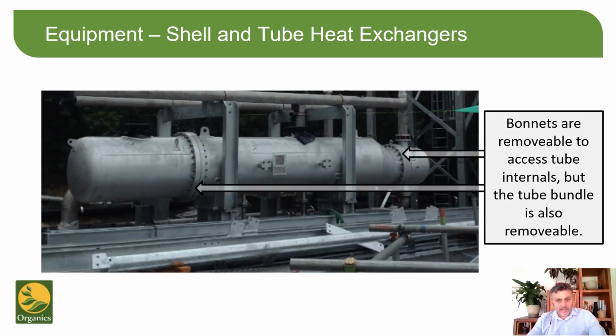All too often, heat exchangers work well on day one, but quickly suffer from performance decline due to soiling. We design using a larger fouling factor, more appropriate to the wastewaters we treat, to ensure extended performance. But we recognise that eventually all things require cleaning, and when they do, it should not be impossible. We ensure that operation and servicing are at the heart of the design process, so our heat exchangers allow access not only to the tubes for rodding, but also to the outside of the tube bundle. Where possible, we manufacture everything in stainless steel, as we found that protective coats on cheaper steels get easily damaged in cleaning.